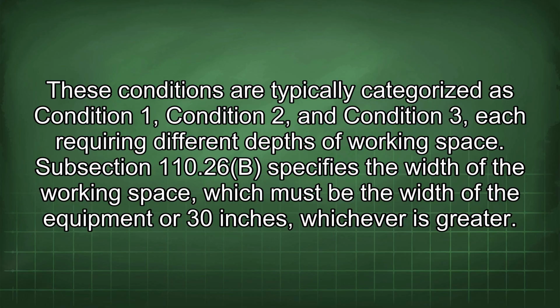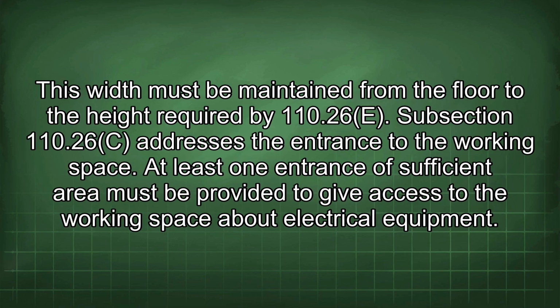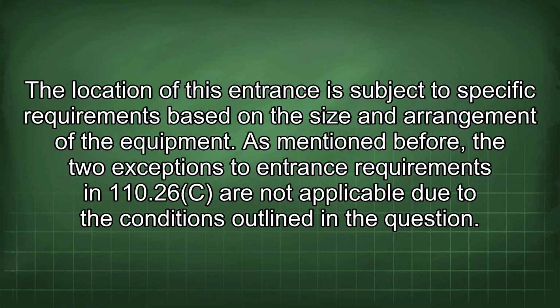Subsection 110.26b specifies the width of the working space, which must be the width of the equipment or 30 inches, whichever is greater. This width must be maintained from the floor to the height required by 110.26e. Subsection 110.26c addresses the entrance to the working space. At least one entrance of sufficient area must be provided to give access to the working space about electrical equipment. The location of this entrance is subject to specific requirements based on the size and arrangement of the equipment.